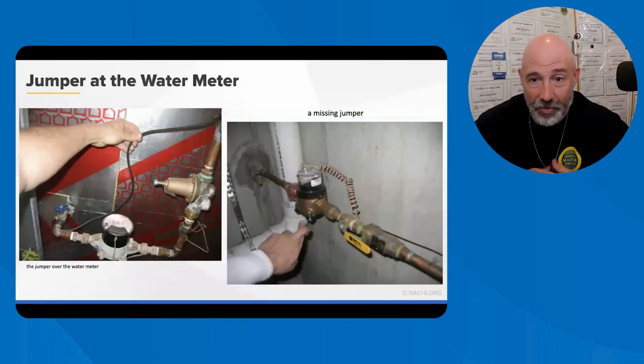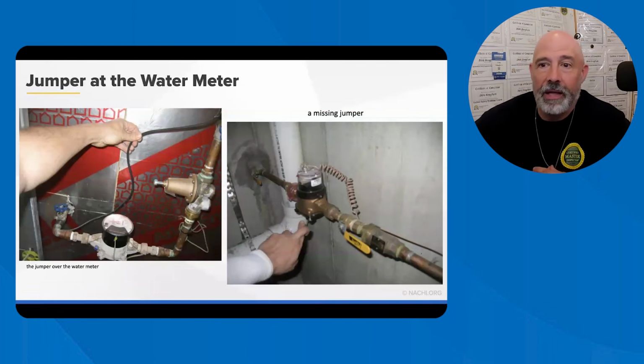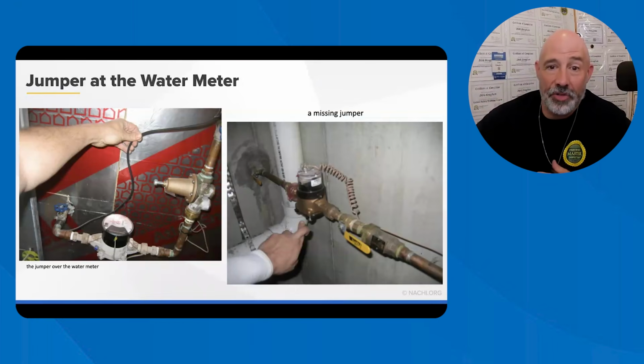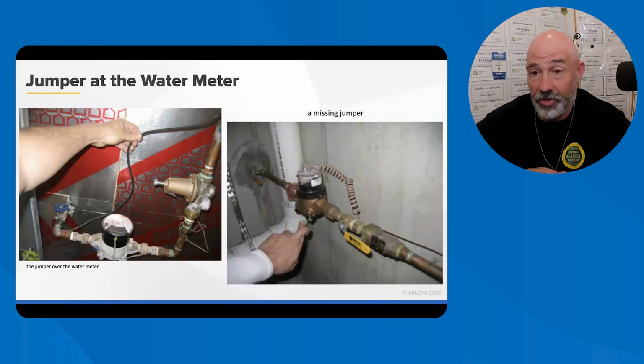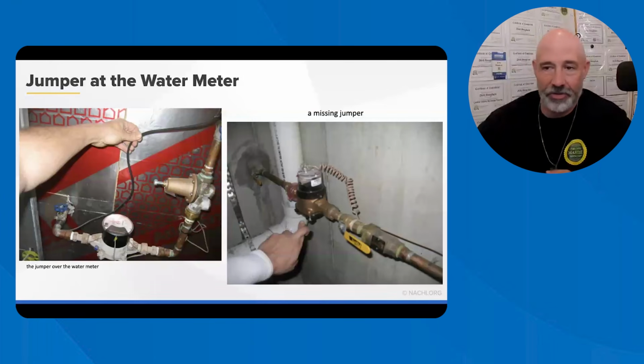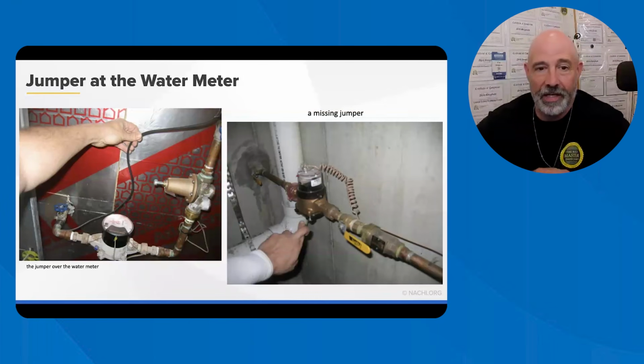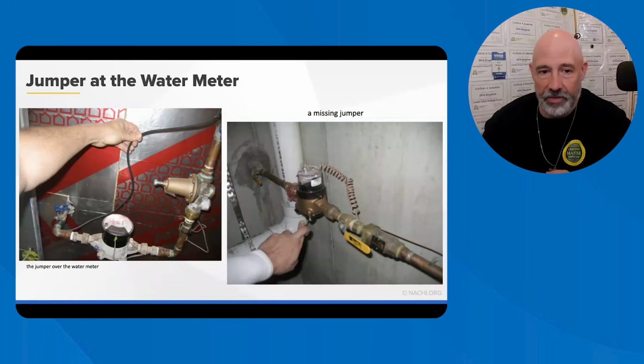For example, a jumper wire may be installed over the water meter because the continuity of the grounding path or bonding connection of the internal pipe should not rely on the water meter. And it could actually blow out that water meter too. So the jumper wire is a large gauge conductor that jumps from the water meter and is securely attached to the metal pipe on the other side. So it just jumps over that. Not shown here, but I already talked about the well casing too. It has to be within great depth, and you can actually use that as a ground too.